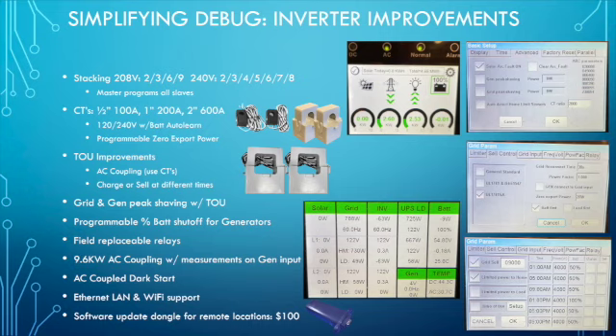That's how we're able to determine the direction and so forth. Okay, we did some time of use improvements. We're able to use the CTs to figure out if AC coupled panels are producing more power than the house is consuming, and then it charges the batteries. It powers the loads in the house, then it charges the batteries, and after that, excess current goes back to the grid. If you also look over here at the right-hand side in the lower corner, you see that we also added a sell column, so we can AC charge off of AC coupled panels, a generator, or the grid, and we can also sell back to the grid on a time-by-time basis.